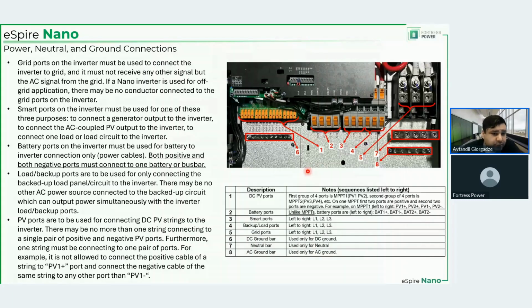What else do we have on this page? I don't want to miss anything. Yeah, one more thing. AC-coupled PV will not end up on the backed-up side of the inverter. You can connect it directly to a smart port, but if you use a smart port for backed-up loads, or you use backup ports for backed-up load panels, the AC-coupled PV should not be connected there, because we will not have the ability to curtail the output of the AC-coupled PV in that case.